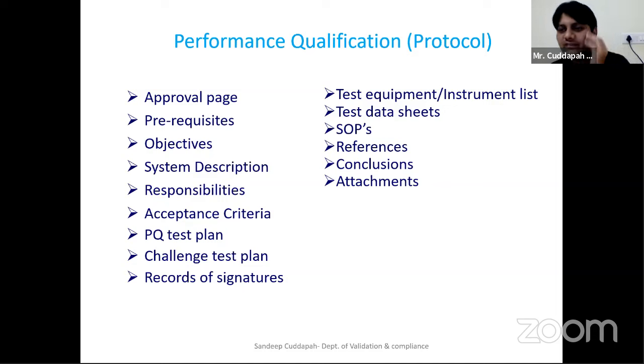In the performance qualification, you will give certain acceptance criteria. If you set 100 RPM, exactly 100 may not come every time. So there you have to give plus or minus, the variability allowed, during performance qualification. That is based on your calibration. That's why I told you calibration is the core part of this validation, because calibration will give you the range of each instrument. That range will be given as a plus or minus variation in the performance qualification.